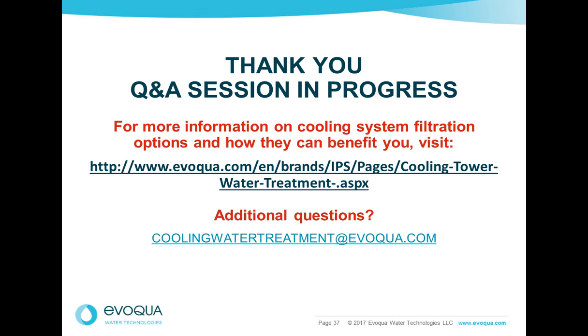Over time, you need a certain size of filter that's going to maintain your system cleanliness and keep up with the dirt load. You could find several dozen papers written on the subject by the Baltimore Aircoil or the International Water Conference. There's just a bunch of papers written on that 3 to 5%. Yeah, I think it's basically from data over the years, and again, it's going to vary. That 3 to 5%, like Bob talked about, go oversize it if you've got a lot of dirt coming in. So that 3 to 5% is a rule of thumb. It's not an absolute. Okay, great.